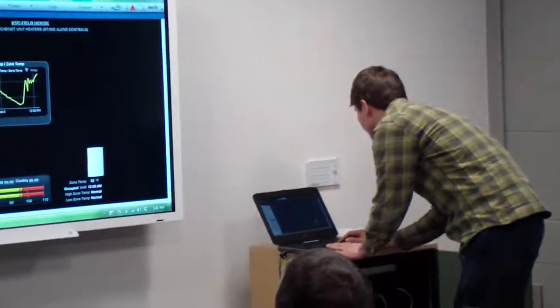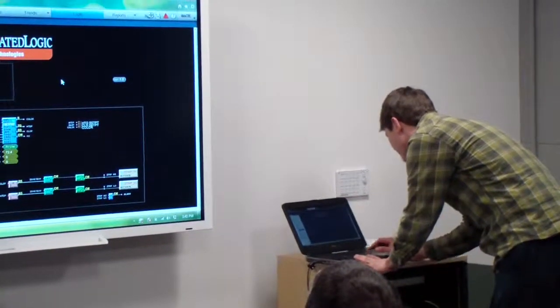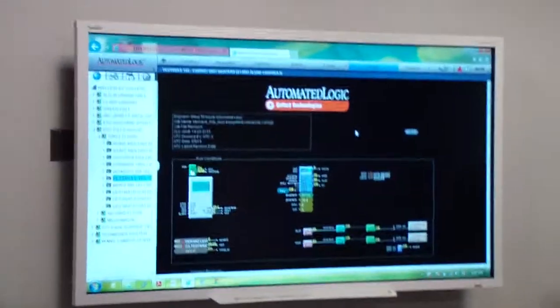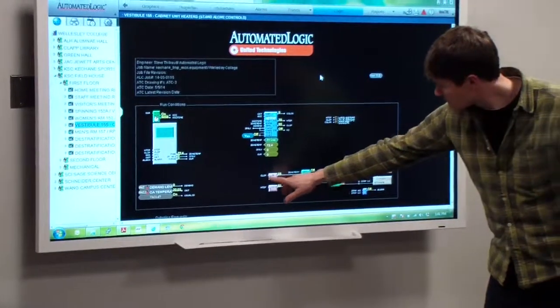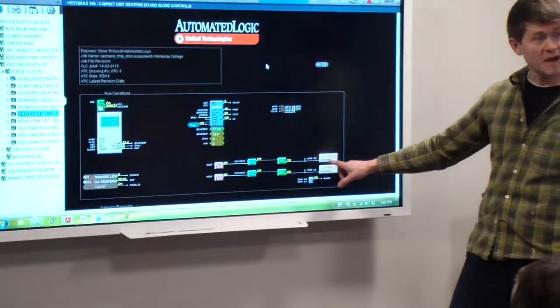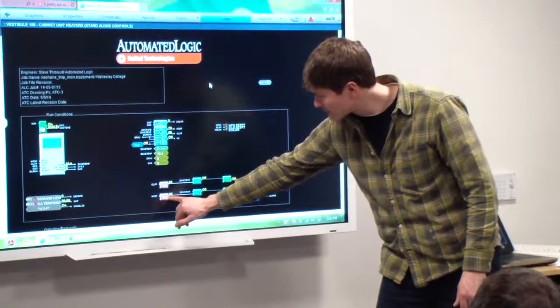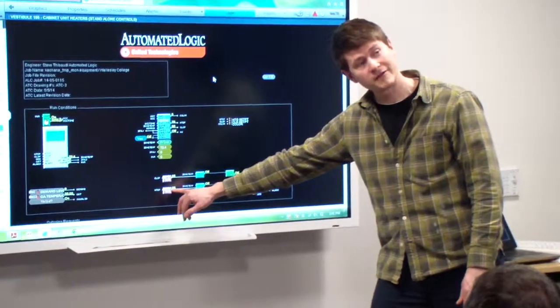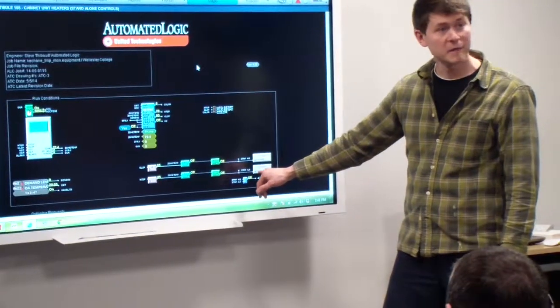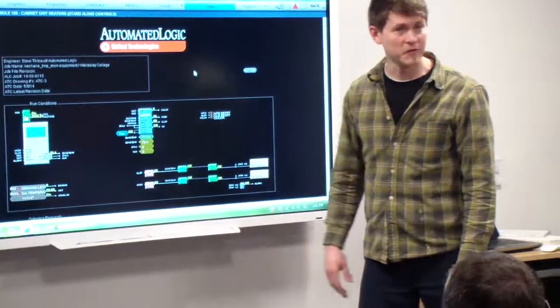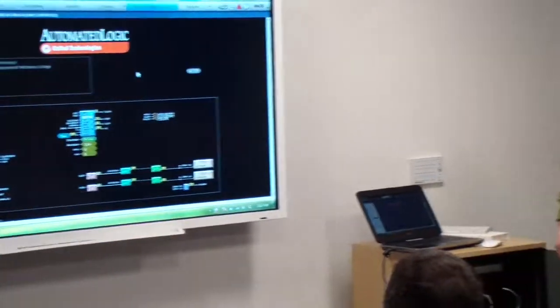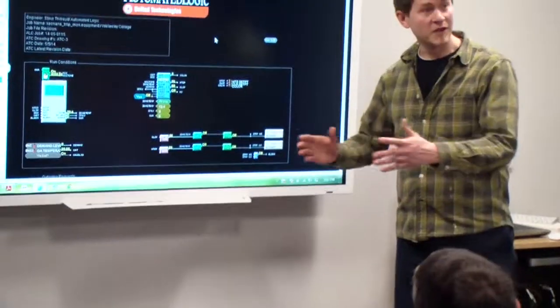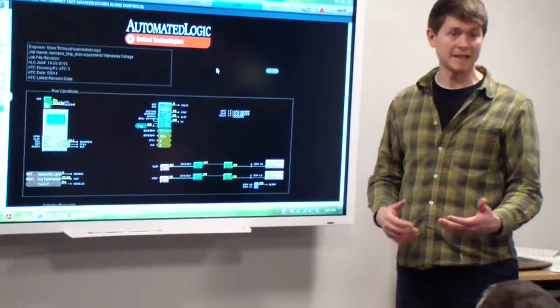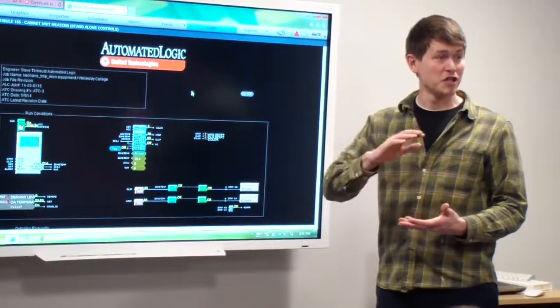Is there an alarm set point on that? Yes, let's take a look at what that is. Right now, your zone temp, if you see in this section here, your cooling would be at 85 before it goes into a high zone temp alarm, and then right now it's 5 degrees below the set point, which is 65. Okay. And that's what will set off your low zone temp. And these are all adjustable. So if you find that you're getting nuisance alarms, you can lower that down, or the same thing with the timer block that's in here. We can expand that a little bit, say that the unit takes a little more time to adjust to the conditions in the space.